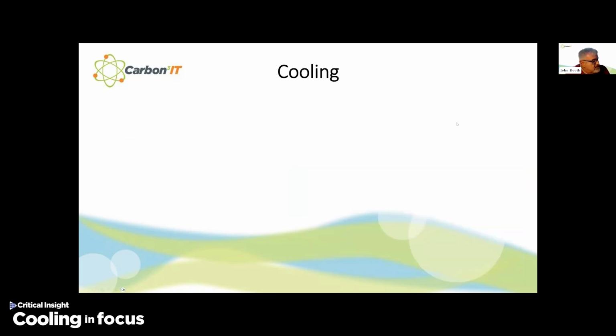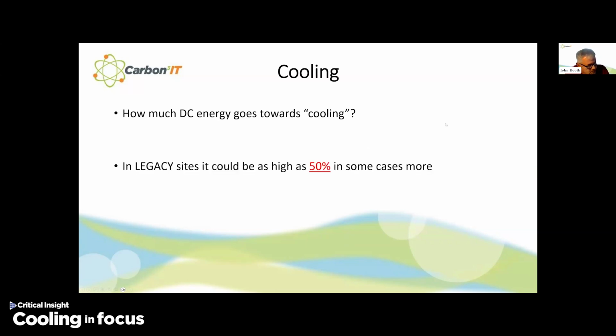operators. So in terms of cooling, how much DC energy goes towards cooling? In legacy sites, it could be as high as 50%, or in some cases more. I've personally been to sites with PUEs of 10, which would indicate that 90% of the total energy consumption is being used for infrastructure, including the mechanical cooling. And in some of the new sites, it could be as low as 10% of overall energy consumption. So that would be PUEs of 1.1. There are many examples of sub 1.1 PUEs as well, mostly in the Nordics because they're adopting free cooling.